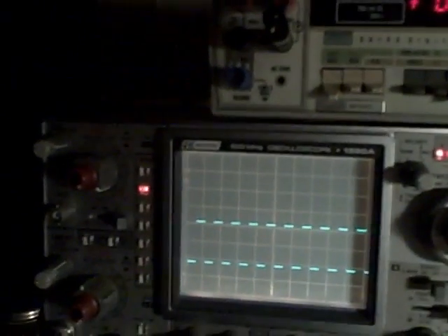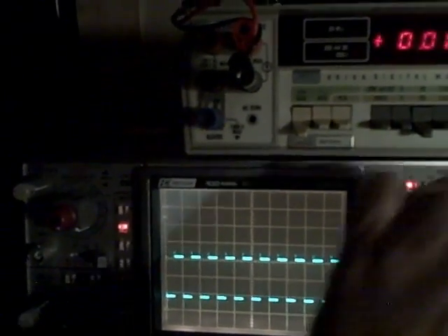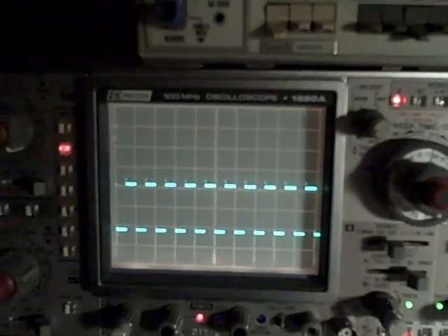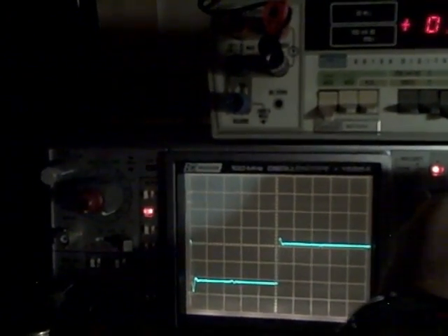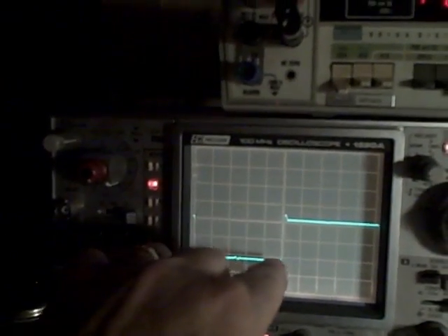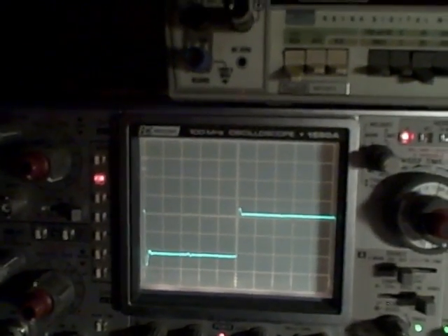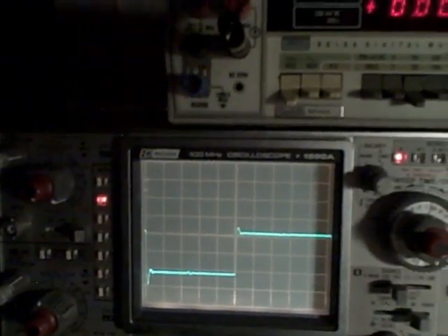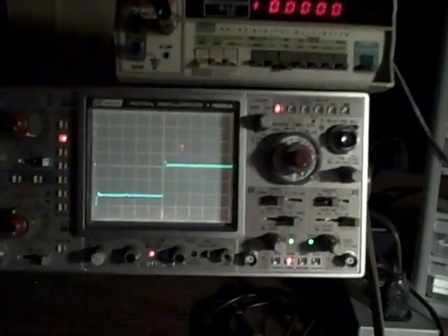Fastest we could go would be 1 microsecond. And let's go ahead and display that. Here we are. 1 microsecond per division. So we have 10 displayed across the screen. And if I go up, raise my scope speed by a factor of 10 again, kick up my brightness just a little bit. Here we see we start the trace, we jump up, we finish the cycle in 10 divisions. So again, we know the scope is calibrated accurately because we're testing it with this calibrator. So that's how you check your horizontal sweep with this unit.